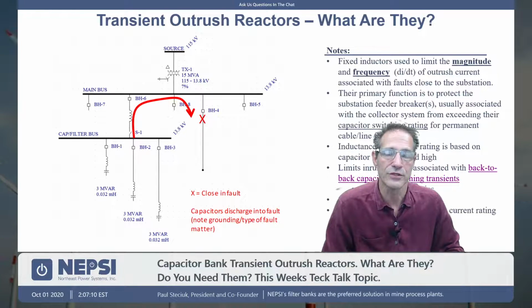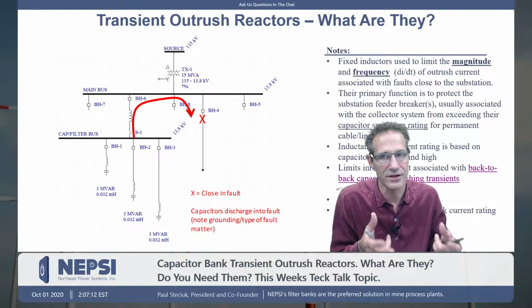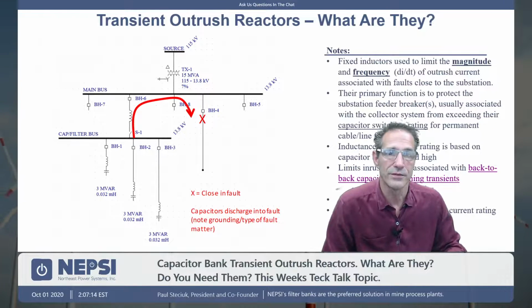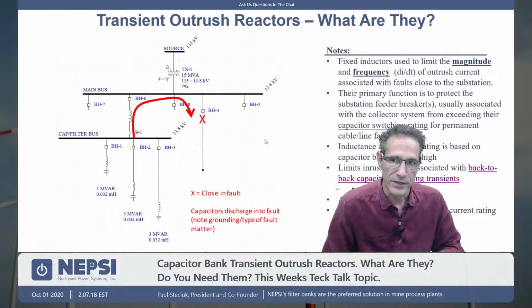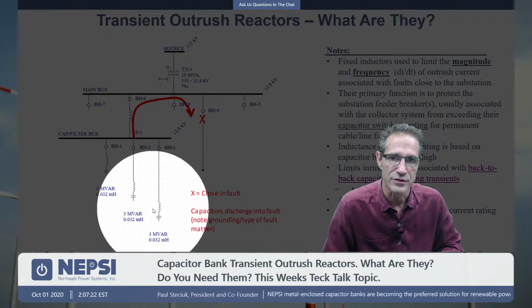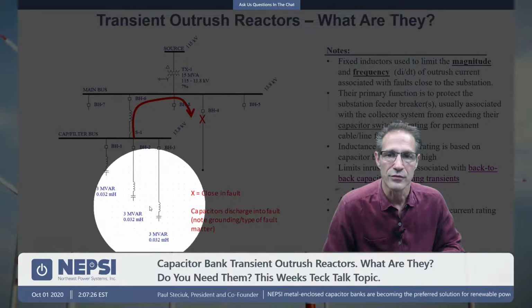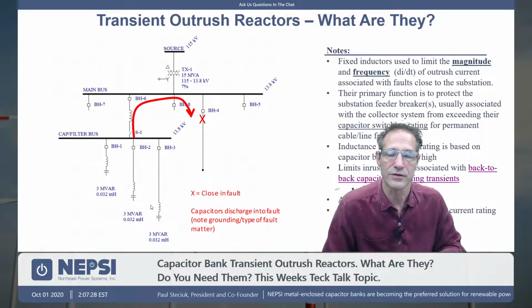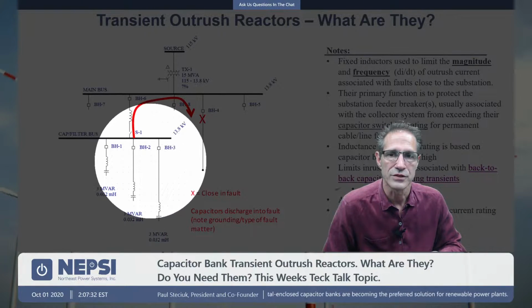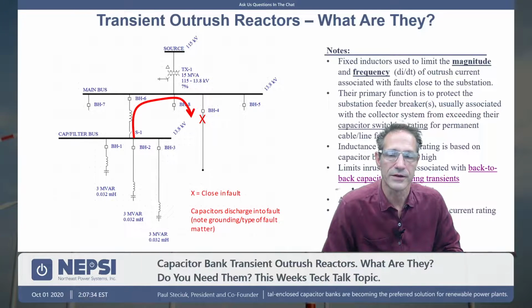Remember, outrush reactors typically have a slightly higher rating than those that might be used for transient inrush to a capacitor bank. So I'm going to put my mouse here and show you. These are transient inrush reactors. And we have a Tech Talk where we talk about these. They're there to reduce the back-to-back switching current that you might get in a metal enclosed system when the switching device closes.